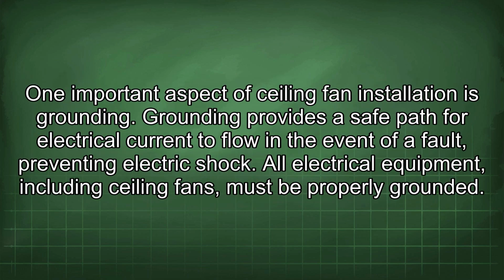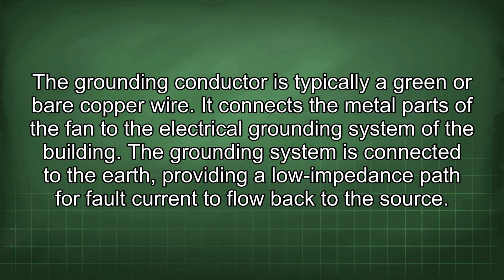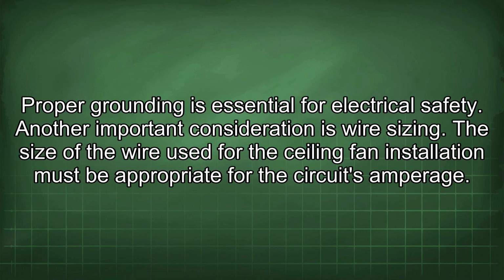One important aspect of ceiling fan installation is grounding. Grounding provides a safe path for electrical current to flow in the event of a fault, preventing electric shock. All electrical equipment, including ceiling fans, must be properly grounded. The grounding conductor is typically a green or bare copper wire. It connects the metal parts of the fan to the electrical grounding system of the building. The grounding system is connected to the earth, providing a low impedance path for fault current to flow back to the source. Proper grounding is essential for electrical safety.